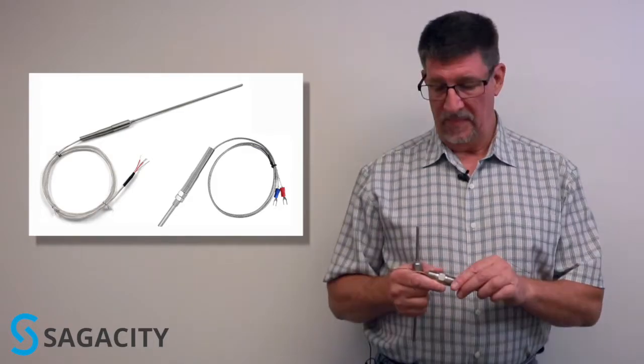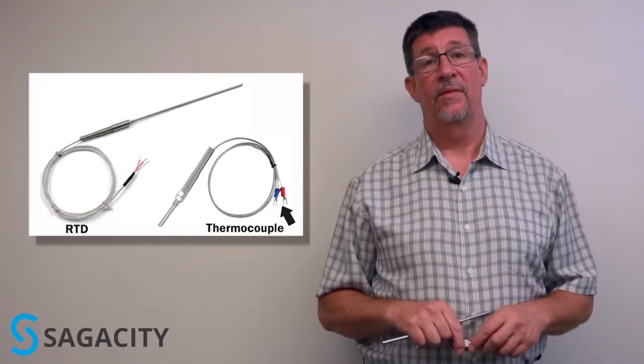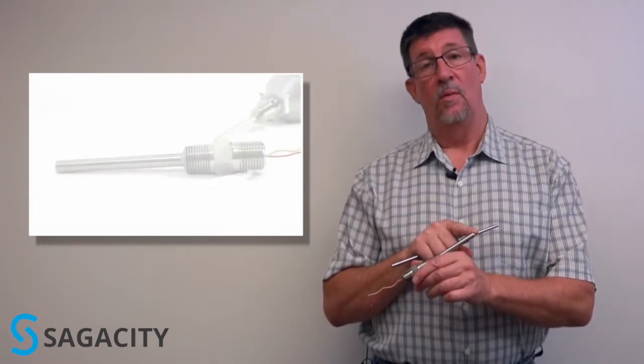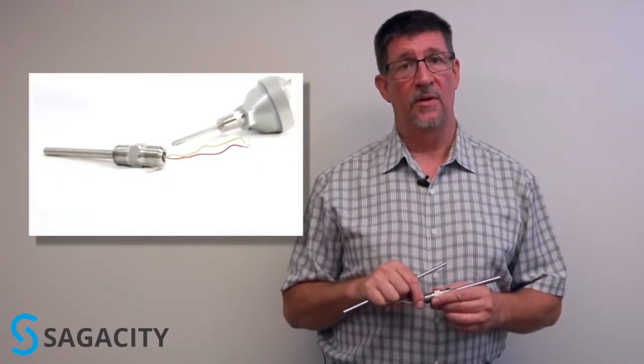A thermocouple will have two wires out the back. An RTD will typically have three or more wires out the back. That's a good way to tell the two of them apart. A thermocouple will have a weld end and we're welding two dissimilar metals together to generate a voltage output.